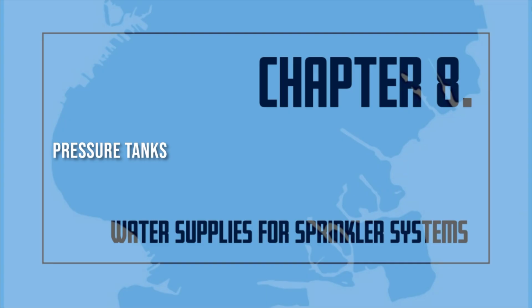Because the water is always under pressure, it can be forcefully distributed throughout the sprinkler system. An important limitation is the small amount of water that can be stored in such tanks. Where a small pressure tank is accepted as the water supply, the system is called a limited supply system. Pressure tanks are often used in situations where an adequate amount of water can be supplied by a public or private source, but the water pressure is not adequate.